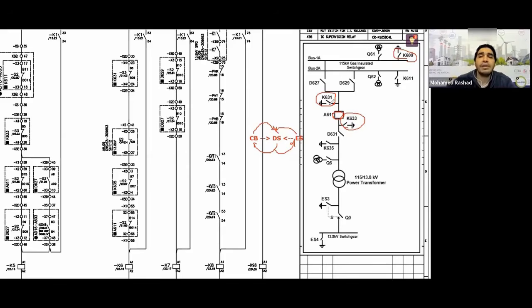So now you have looked at the ground, K609, K631, K633. What about the three of them? They are open, good. And what about the breaker? It's open. Now you have ensured that the grounds are open and you have ensured that the breaker itself is open. Why? Because you are worried if the breaker was closed, voltage might pass through you and it might go and affect other loads, right? I told you, right? So you ensure the breaker is open.